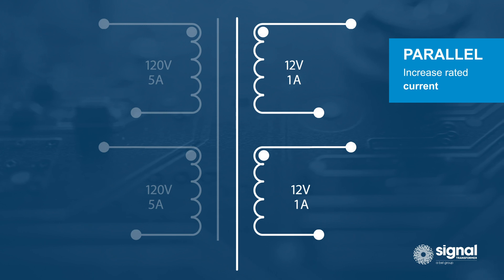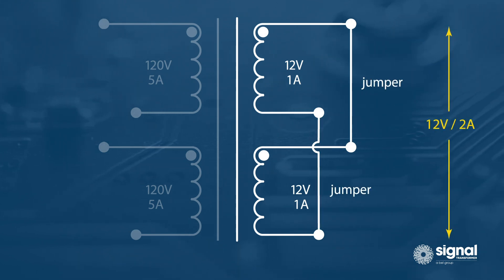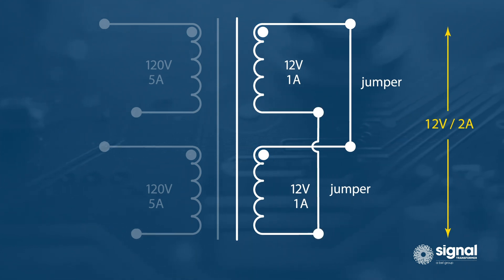Multiple windings can also be connected in parallel to increase the rated current without changing the voltage. Connecting two 12-volt 1-amp secondary windings in parallel by connecting starts to starts and ends to ends produces a 12-volt 2-amp output.